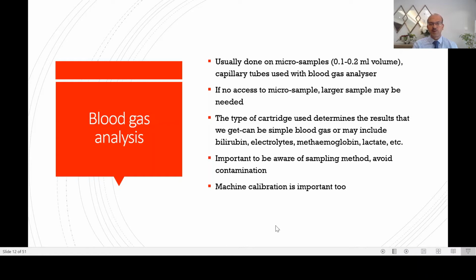So we can add bilirubin, electrolytes. If you're on nitric oxide, methemoglobin measurements help you. Measurement of lactate will be useful as well. It's very important to be aware of the sampling method, and we should be clear to avoid contamination. Calibration is important. Sometimes the machines calibrate when you're taking the sample, so you should be aware of the routine when the calibration happens, whether it is automatic, whether the lab personnel comes and does it on your lab.